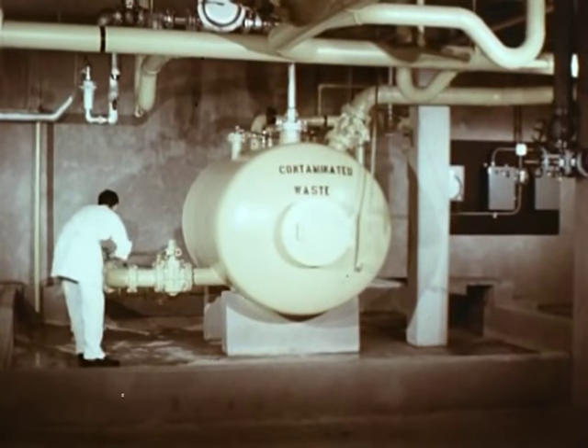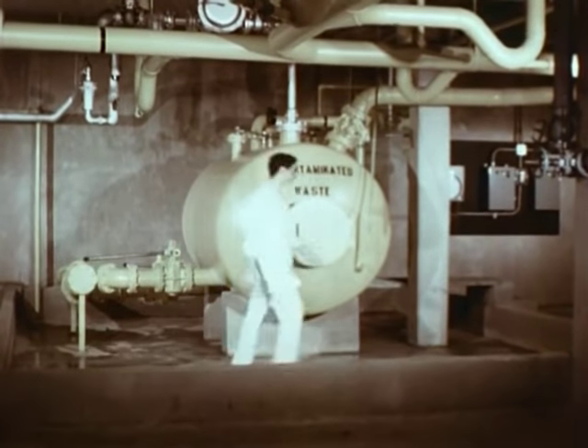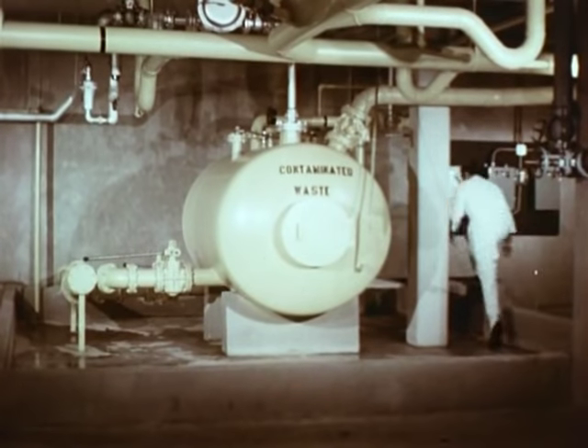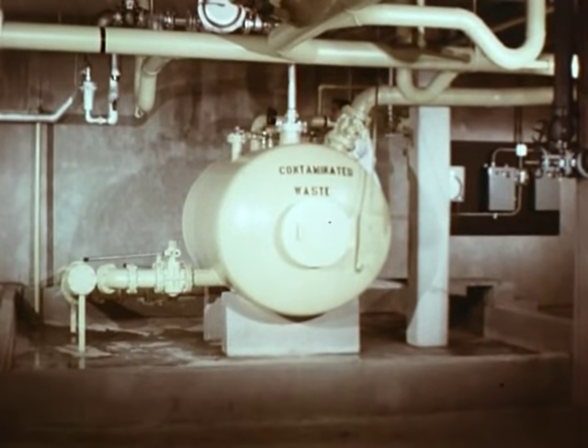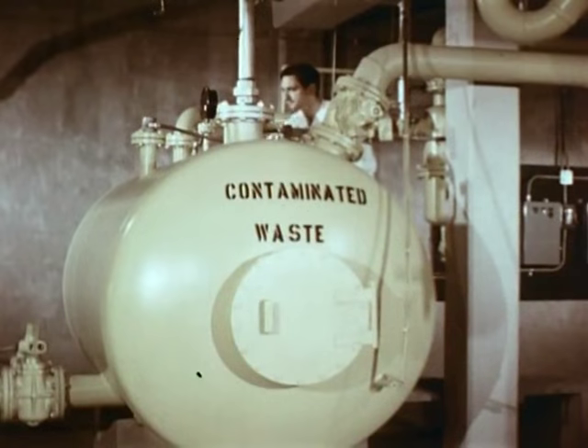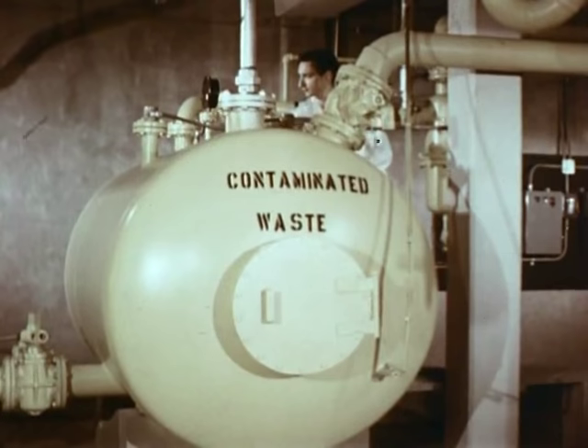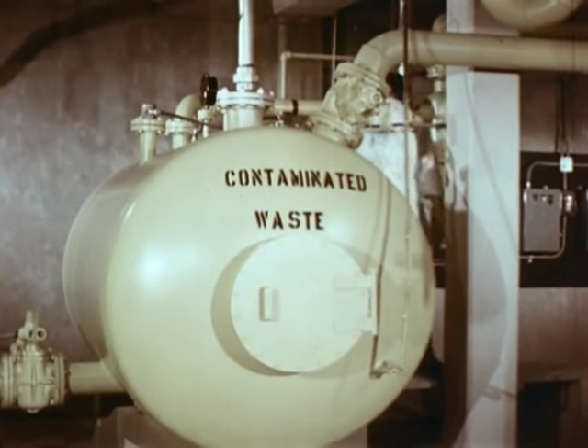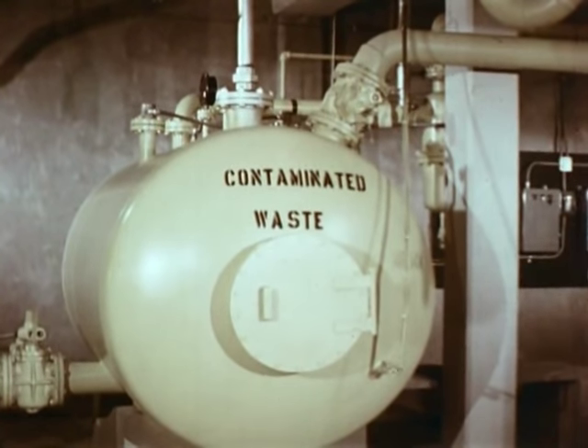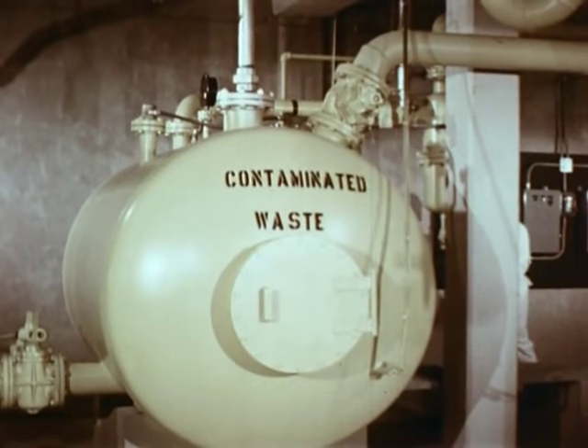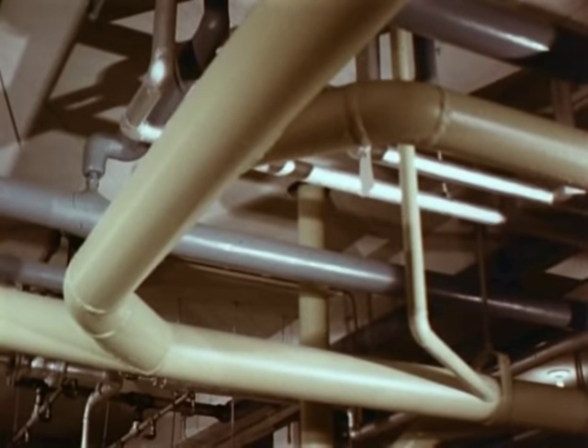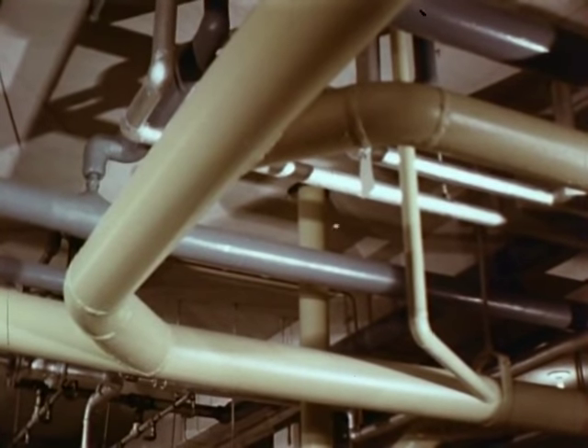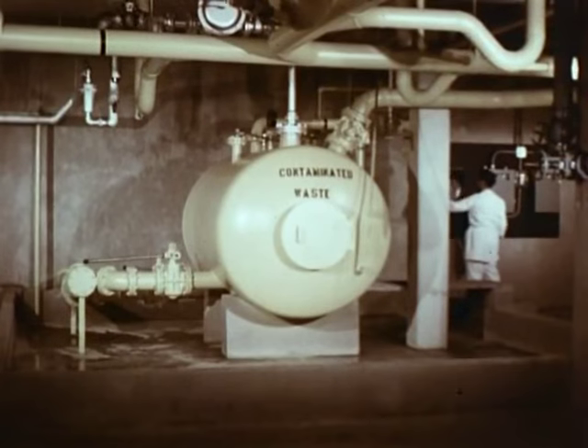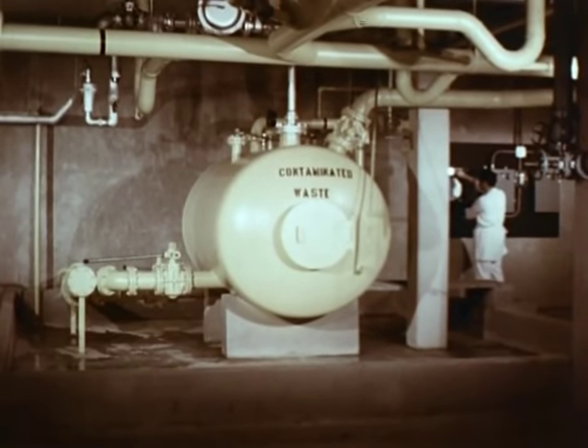In some laboratories, facilities must be provided for treating contaminated liquid wastes. Two basic systems are employed, the batch and the continuous flow. The batch system, shown here, is used to collect wastes from infected animal areas. Liquids flow by gravity to the tank, where they are sterilized by adding steam and holding for a period of time. The piping should have welded joints to assure no possibility of leakage. Note that a concrete curb has been provided to contain the liquid in the event of a rupture in the system.